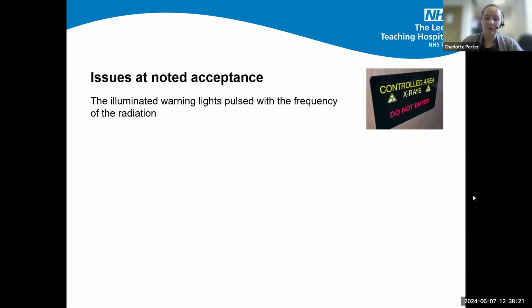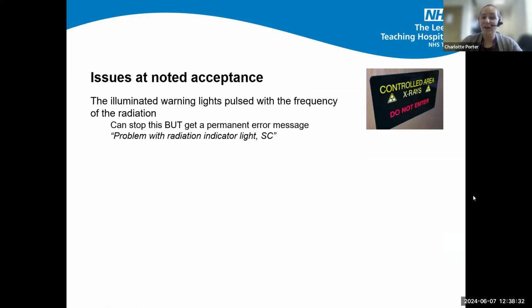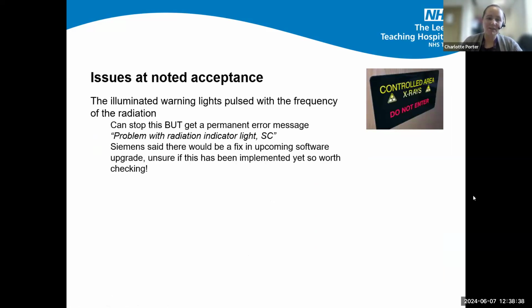So quickly, a few issues that we noted that I thought were worth mentioning. When it was installed, we found that the red part of the illuminated warning light pulsed with the frequency of the radiation. They did have a fix for this, so we asked them to instigate that, but it did give us a permanent error message. Siemens said that there's a fix in upcoming software upgrades. To be quite honest, I've not been down to our system to check whether that's been implemented yet or not, so it's worth checking to see whether that pulsing still happens and if that error message is still present.